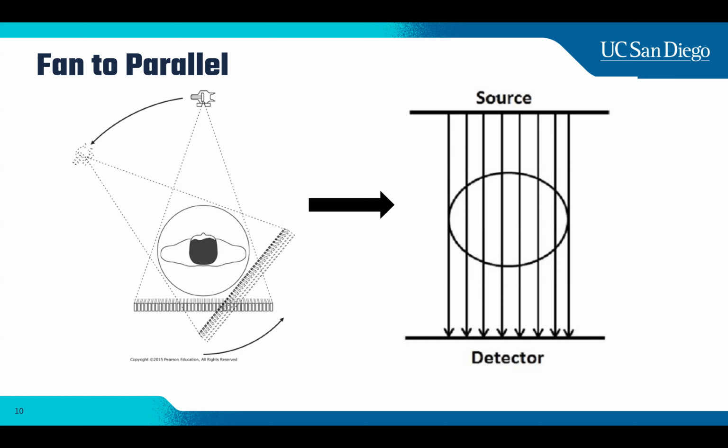However, our detector in the GE system has a curve on it, right? So it's not exactly this geometry that we've got here on the left. Okay. And so that might be distorting some of the views such that you get this smearing of data all around in a circular direction. But you would think towards the center, it would be less evident, right? And so your image should really get better as we go to the center. Yes. Well, so there's probably something else going on as well.